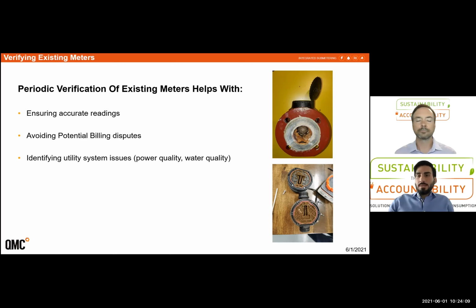Hard water or untreated liquid within the hydronic loops typically degrade the accuracy of these meters, causing them to slow down or report lower volumes. So it's very important to validate the accuracy of these meters periodically. We typically suggest every 1 to 2 years. Next slide, please.